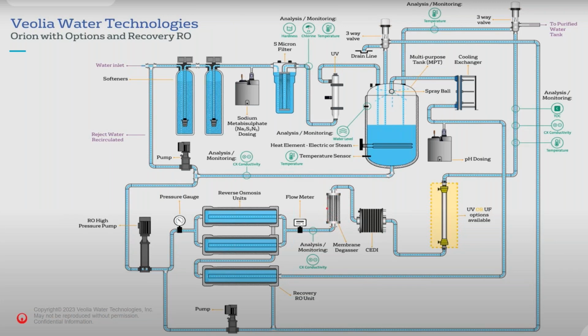The degasser works like a hollow fiber membrane where the water passes through one way and clean instrument air passes down the other way, and it strips out the CO2 through the membrane from the water. The water then passes into the CEDI, continuous electrodeionization unit, which removes any prevailing ions within the water from the RO unit. The RO unit typically gives maybe 20 to 30 microsiemens. Obviously, we're looking to get to less than 1.3 microsiemens.